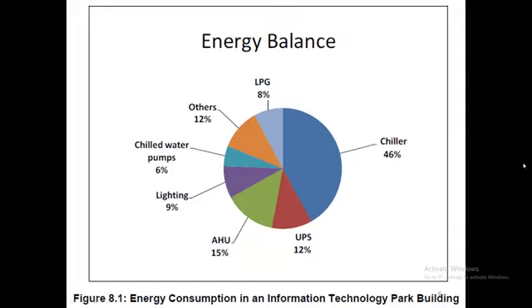Then comes the chilled water pumps, which I will also cover in depth. EEE doesn't mean electrical and electronics only - any system, whatever the prime mover, whether electronic or an electric motor, the load side decides the energy consumption, and there is scope there. If the consumption is 100%, almost 3/4 of the energy savings can be achieved on the load side, and only 1/4 on the prime mover side.